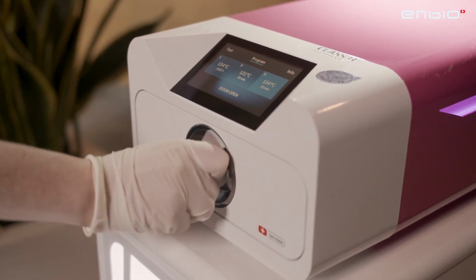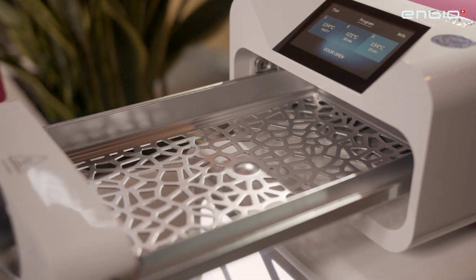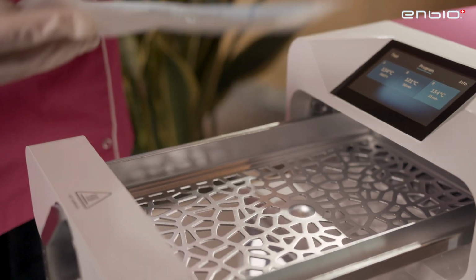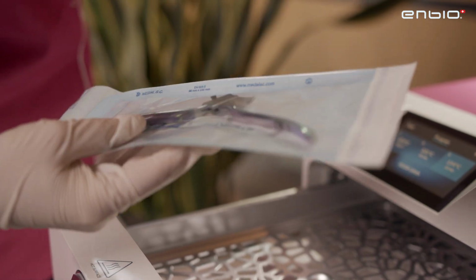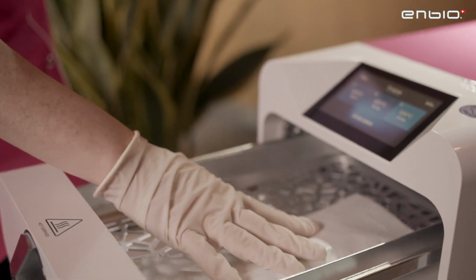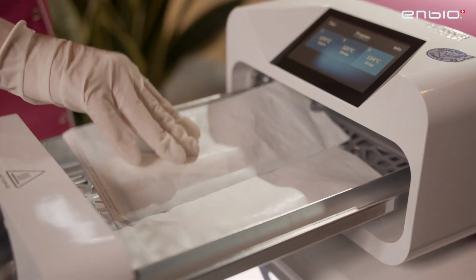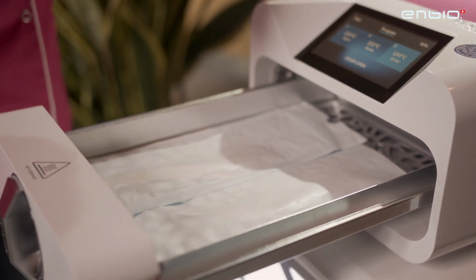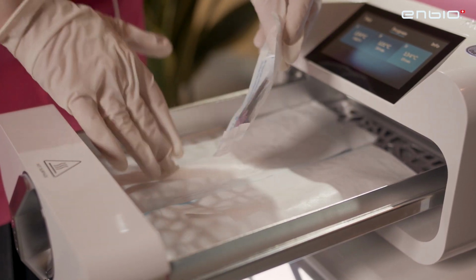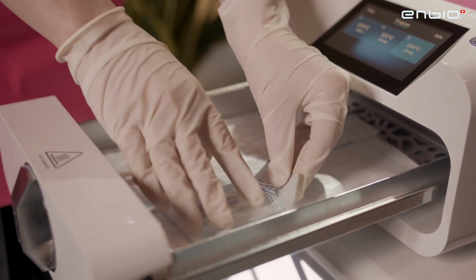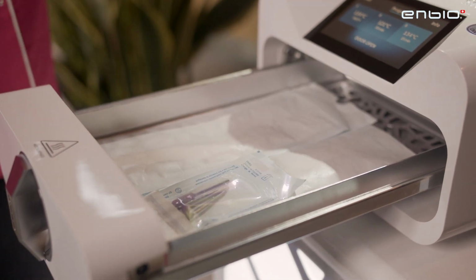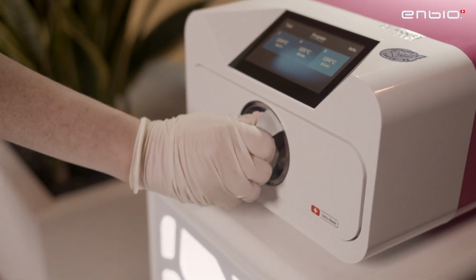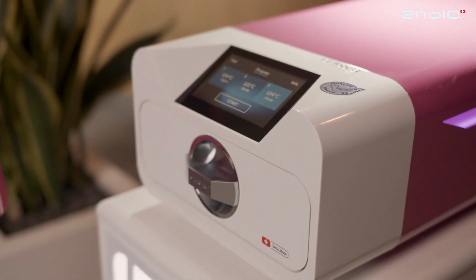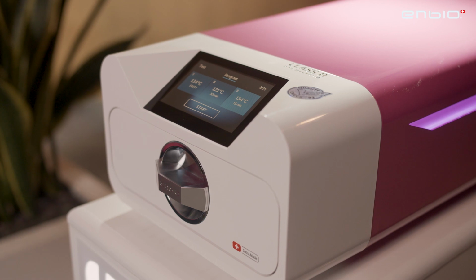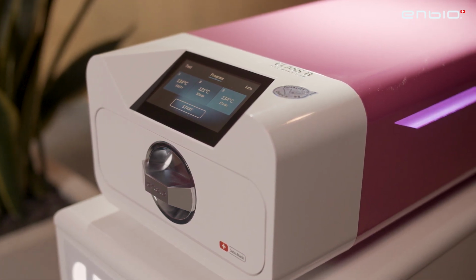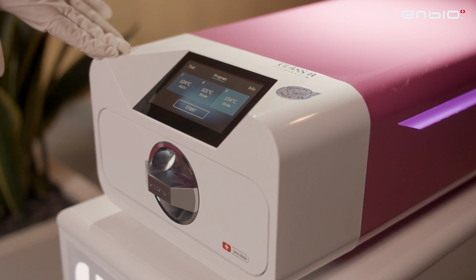First, we open the door. And then if we are using this type of sterilization pouch, it is important to put the foil side down at the beginning. And if we are using another row of tools, it is important to put paper on paper and foil on foil. So practically here I will put the second row like this. Now I'm closing the door. And now we should choose the proper sterilization program. And let's see first what is the difference between the 3 sterilization programs of the Enbio autoclave.